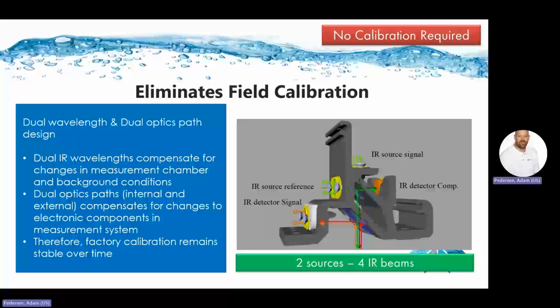The GD10P relies on infrared technology being emitted, reflected, and detected within gas detection paths of the device. The device calculates the amount of gas present against the amount of infrared light absorbed when reflected off a mirror within the gas detection path. To help reduce false alarms, the GD10P has been designed with two infrared paths, the detection path and the reference path. This allows the device to differentiate between gas and other contaminants. The device is then able to adjust the zero drift that occurs in the event of contamination. Therefore, factory calibration remains stable over time. So I should again note that all the optics are mounted on one metal platform you see here, making it immune to vibration. Therefore, the unit does not need to be calibrated.